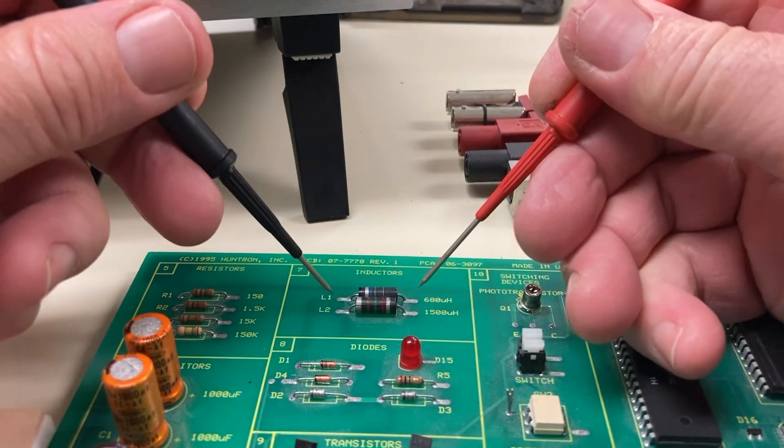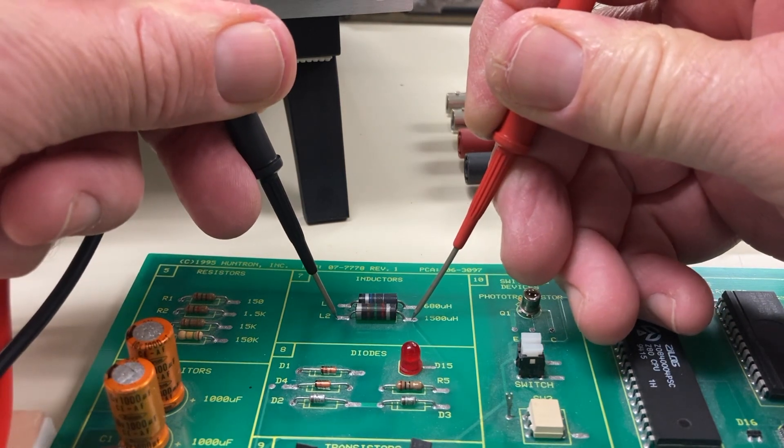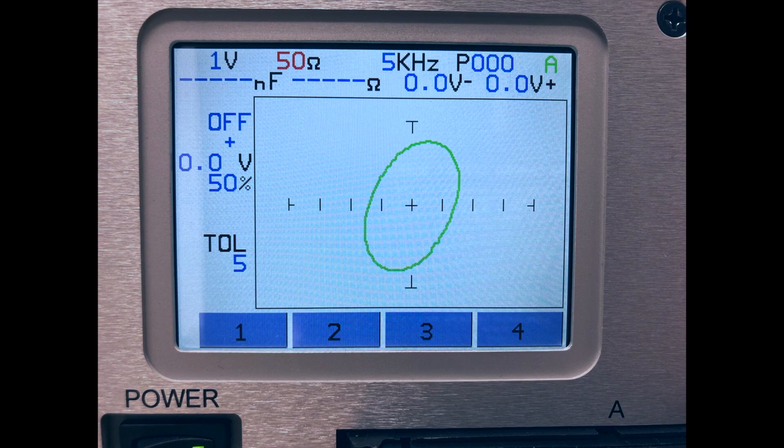Inductive components generally provide signatures similar to capacitors, but the adjustment of the range settings is somewhat different. As the value gets smaller, the resistance range decreases and the frequency range increases due to the reduced number of wire turns in the component.